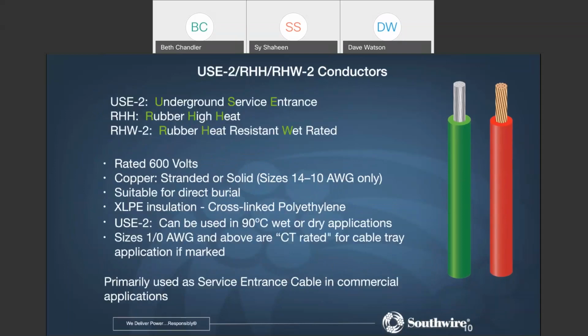Now, this is a triple rated product that is rated as an underground service entrance conductor, meaning it can be direct buried. And then it's also listed as a RHH, RHW style conductor. Now, where did that come from? That's a legacy wire type from back in the days where the conductors, I believe, were actually made with a form of rubber. Nowadays, cross-linked polyethylene is used to fulfill this requirement. So the RHH, RHW designations stayed in place, even though the products are no longer made with rubber.